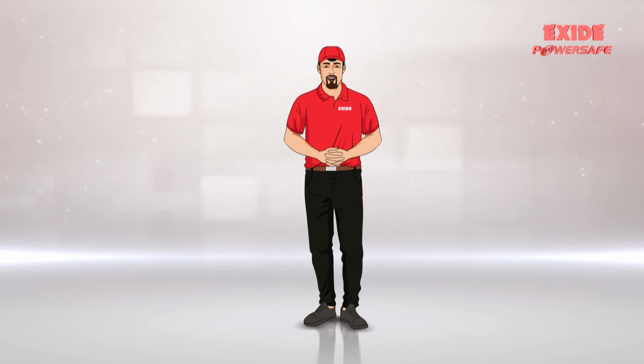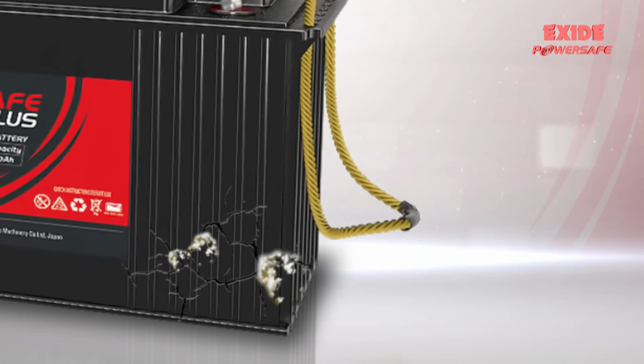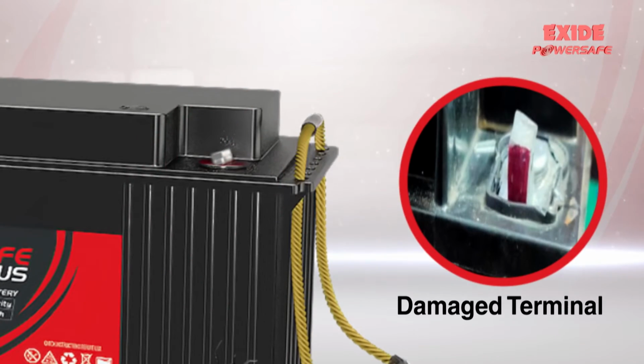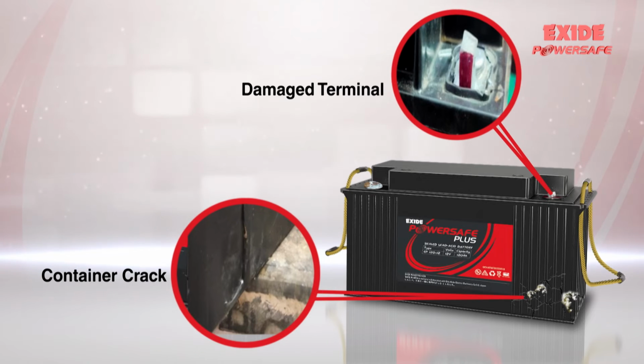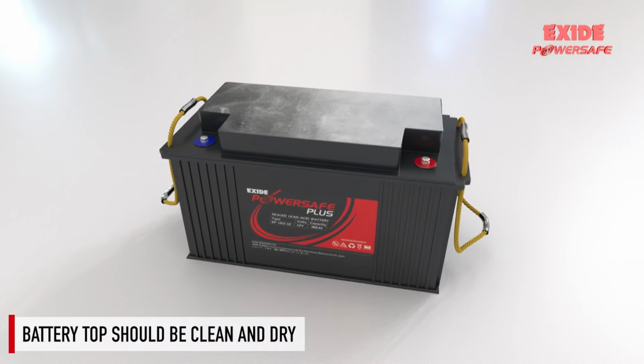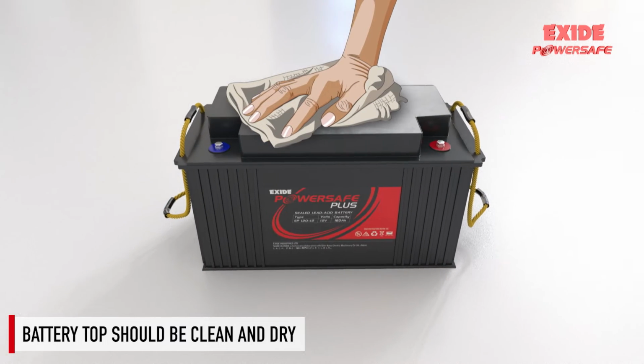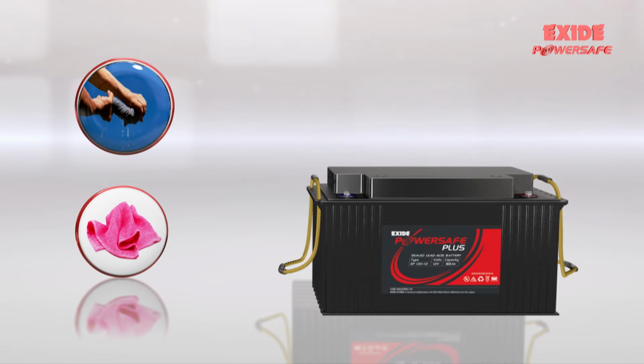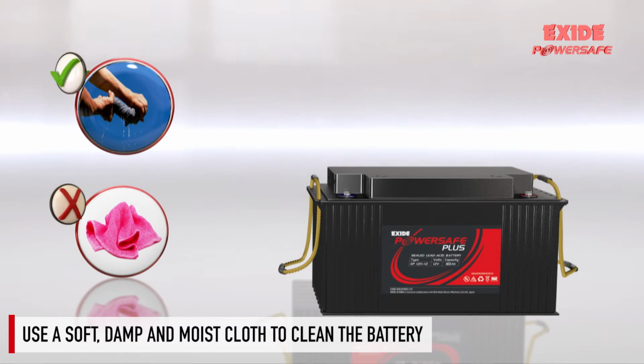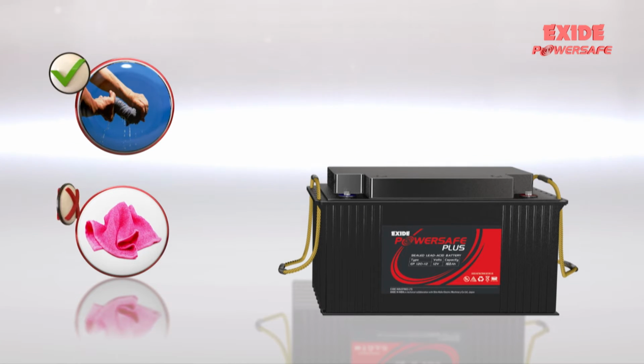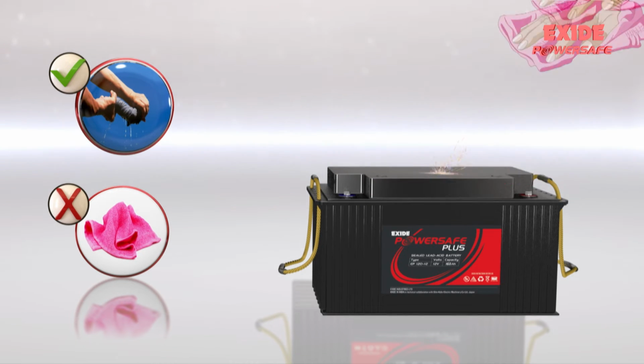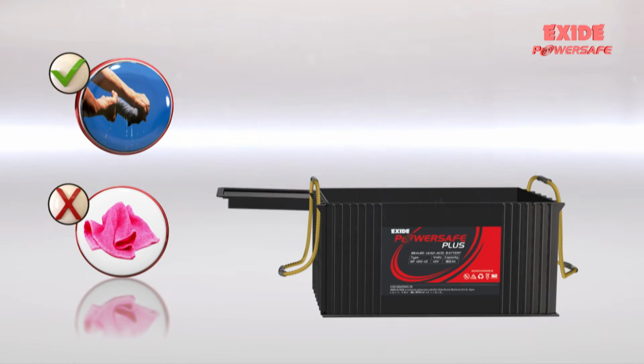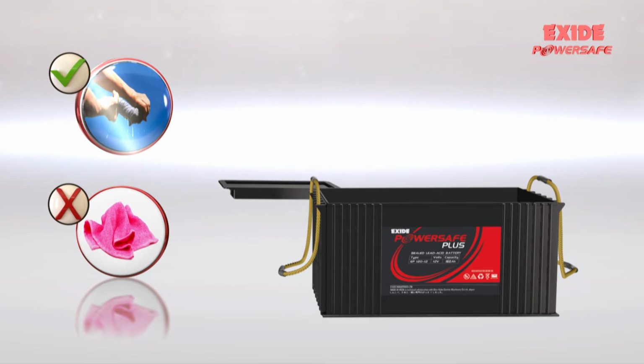Post-unloading and during unpacking the batteries at site, one needs to check all batteries for visible defects such as cracked containers, damaged terminal posts or other unrepairable problems. If any of these defects are found, please contact EXIDE service. The battery top should be clean, dry and free of dust to prevent blockage of the vent holes. While cleaning or checking the VRLA batteries, always use a soft, damp cloth containing adequate moisture. Never use a dry cloth as sparks created by static electricity can ignite hydrogen gas generated from the battery, which could lead to an explosion.